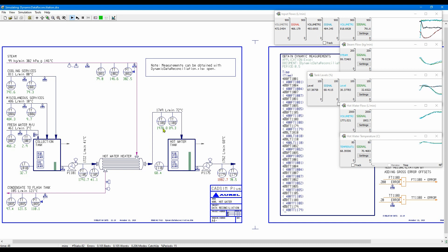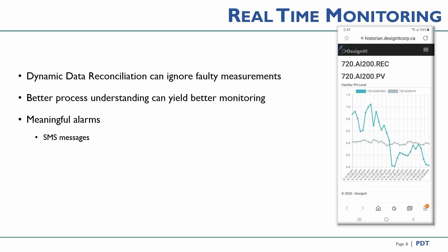When I start running again, these measurements are out. There's now a reading of 1,989, but the simulation is still marching along, knowing that those are wrong, and it can figure out from the rest of the measurements what is really happening. Here is an example where dynamic data reconciliation was able to ignore a faulty pH meter, but when the caustic pump failed, an SMS message was sent to my phone. A screen capture of that phone shows a trend chart of the measured and actual pH for the last five minutes to go along with that alert.